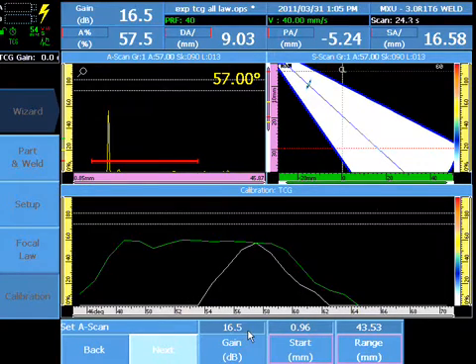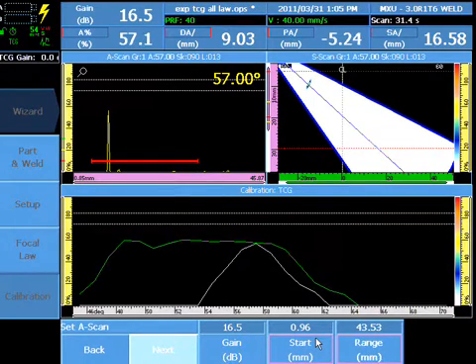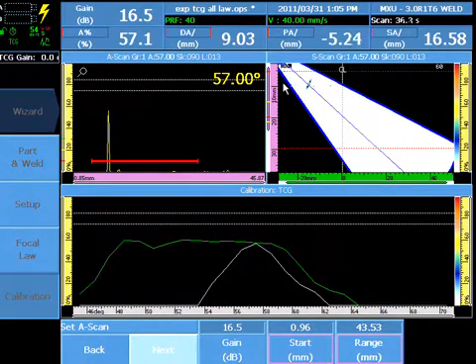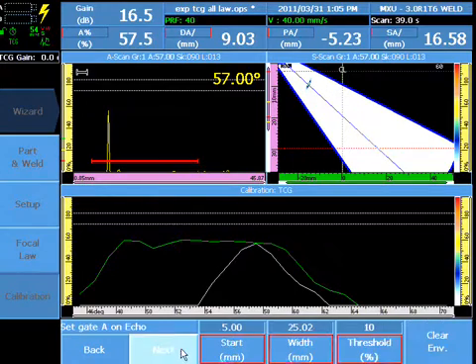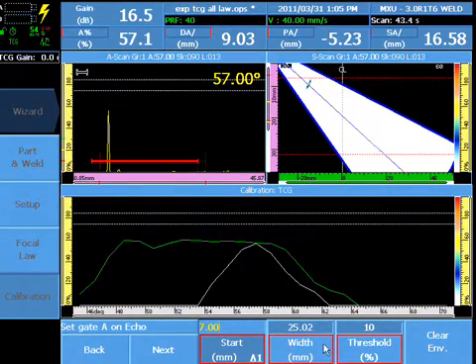Ensure enough gain for approximately a 40–70% signal is present, and ensure your range covers the entire calibration target for all focal laws. Set the gate position over the first calibration target.